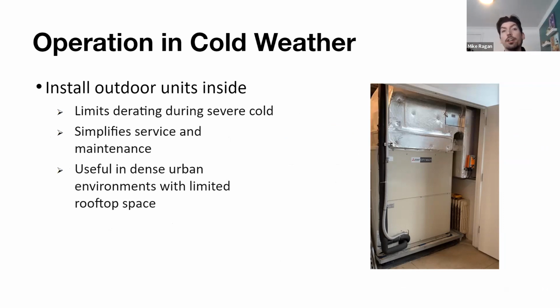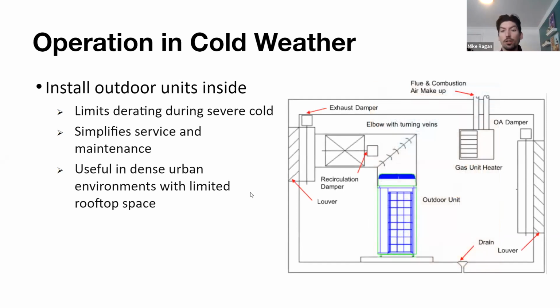So another way that we can eliminate the derates we would see on cold weather days is to actually install your outdoor units indoors. So here's an example. Here's a picture of a VRF outdoor unit. I'm using outdoor unit in air quotes there because it's inside. For this particular instance, here's a schematic overview of what this would look like, where we have a gas unit heater in the space that's going to be tempering the air. So the outdoor unit is not going to be seeing 0 degrees when it's 0 degrees outside. If you have a gas unit heater set up in here, set to 40 degrees, well, that outdoor unit is only ever going to see mild heating conditions over the course of the year. You're going to mitigate the derates associated with that unit in that particular climate.